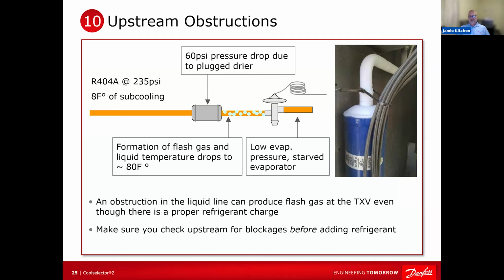So why is it then that when you have 0 subcooling at your metering device, you don't check upstream of your TXV, you just dump more refrigerant in? Can you imagine if people did that with electrical? Oh, I've got 0 volts at my relay, I'm going to put 2 transformers in now to supply power, right? Without ever checking it. Nobody would ever do that, but we do it with refrigerant. So if you have flash gas at your TXV, in other words, you take that measurement and the TXV is hunting, find out where that subcooling went. If you've got subcooling at your condenser outlet, find out where it went.